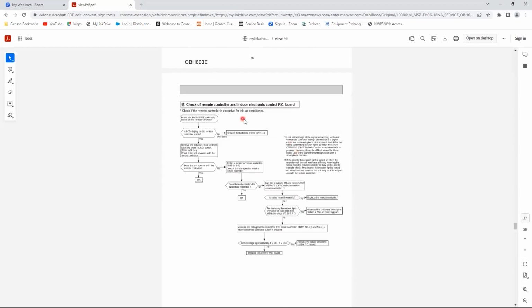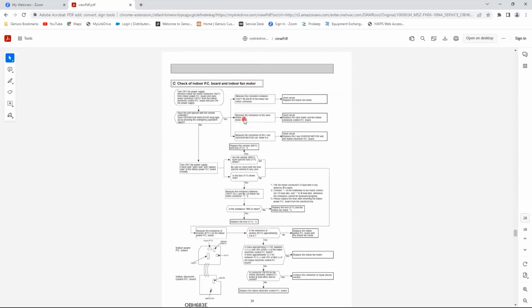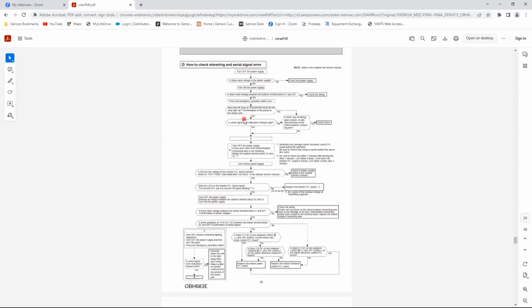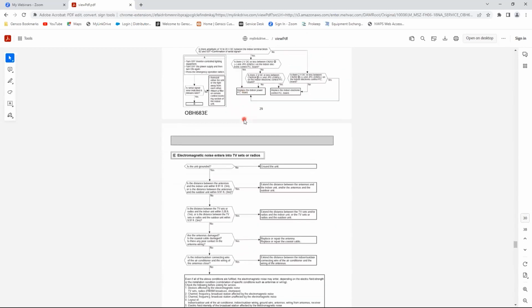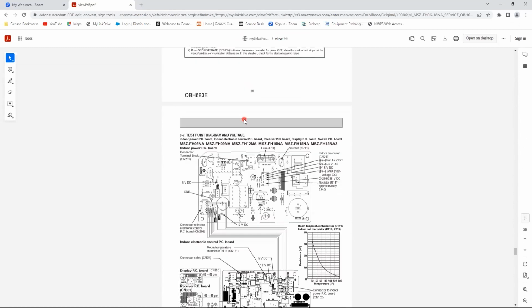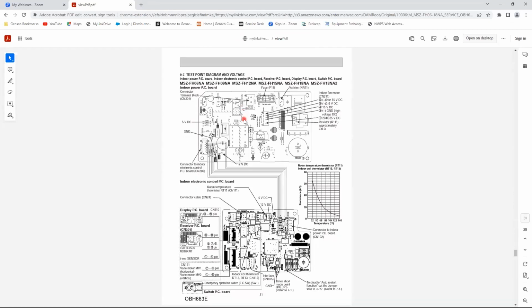Simple as that. So we come down here, PC board, shows you how to troubleshoot miswiring. And here is our 9-1, our test point diagram. It calls out all of your test points and what you should see, what the connector numbers are, and what you should see for voltages.